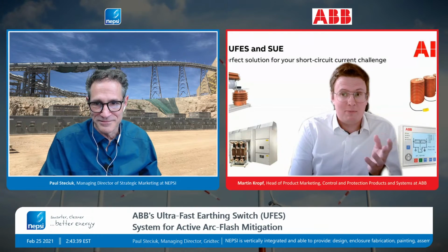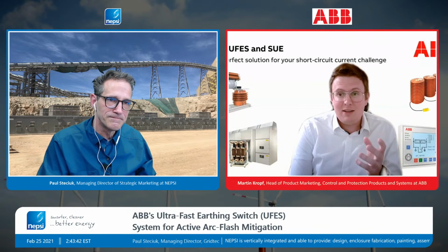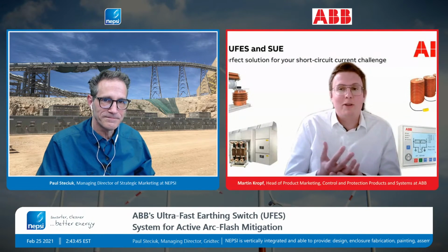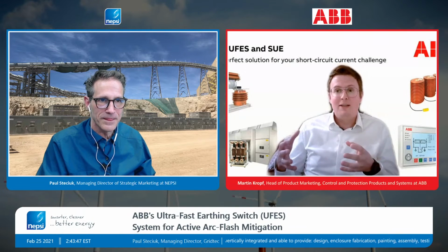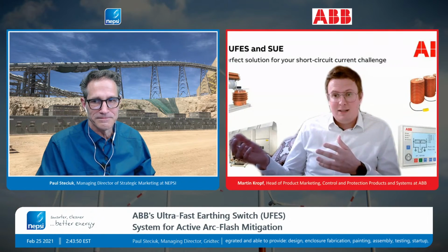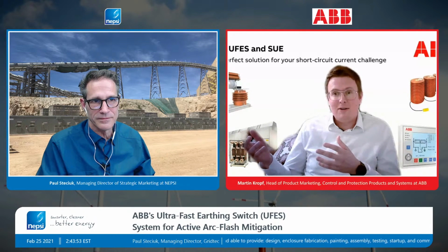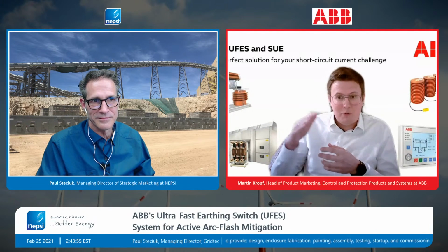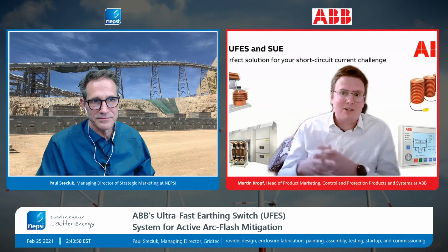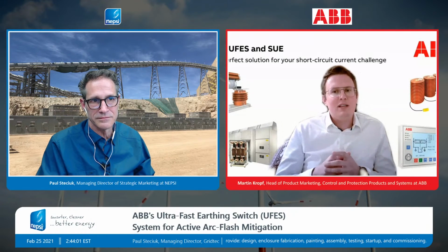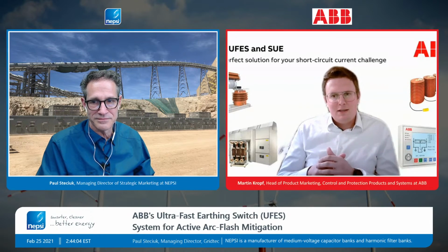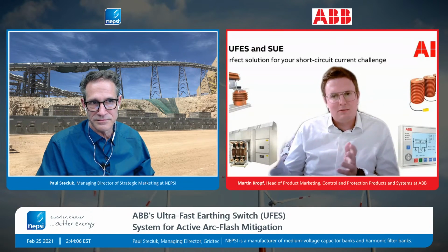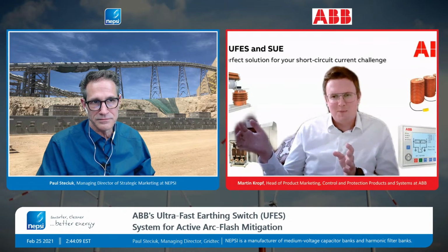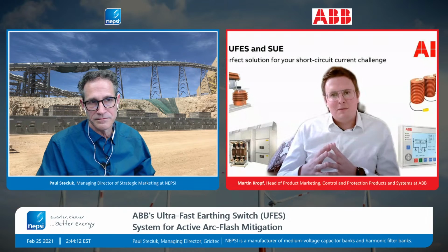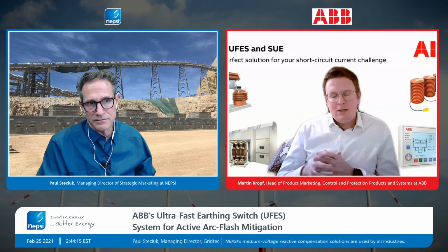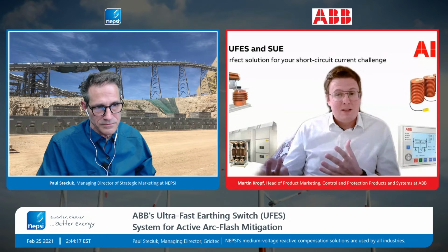a circuit breaker, we are by far faster. Because what we are looking at is current, real current flowing, and light. And we are looking at light and current in less than 2.5 milliseconds, the first 2.5 milliseconds. It may be that there is some protection, like differential protection, which is also seeing that in that fast time. But if it's reacting with a circuit breaker, this takes another 80 milliseconds.